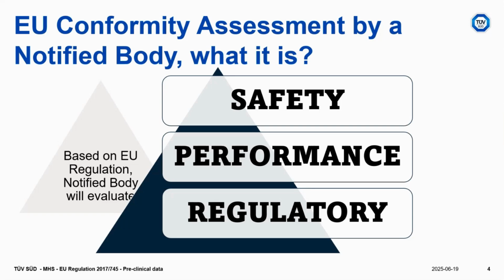So the functions, the properties, the characteristics, any claim given by the manufacturer in the labeling, in the promotional material, in the instructions for use, in the technical specification, shall be demonstrated. So the conformity assessment is not only focused on saying, okay, this device does not do anything bad, but also that this device will do anything good which is claimed by the manufacturer. And the performance can come from applicable standards, but can also be a specific definition and claim by the manufacturer. During the conformity assessment, safety and performances are assessed by the notified body.